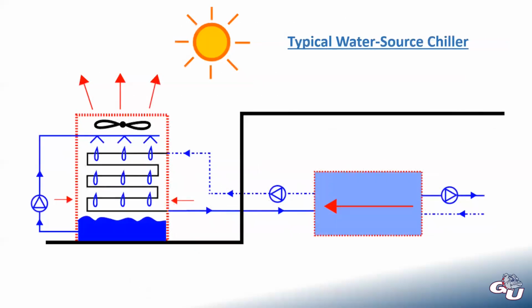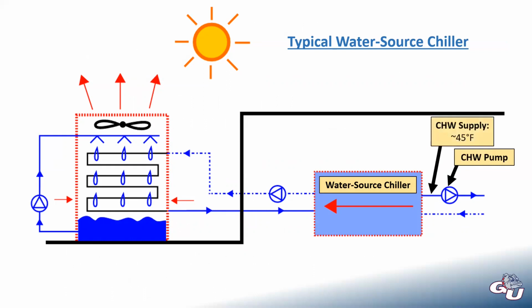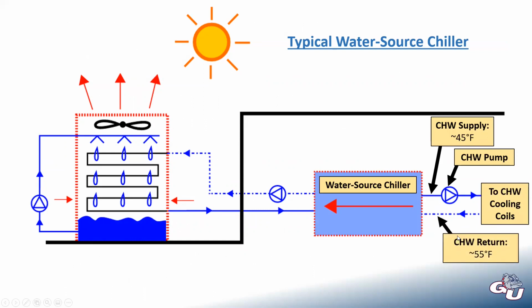Here's another one of my sketches, but you're quickly going to realize there's a lot more going on with this system. We have our water source chiller, which is inside the building. We have our chilled water pump, which is sending out 45-degree water, going out to the chilled water cooling coils, coming back a little bit warmer, goes through the chiller where we chill the water down, and then it sends it back out. On this side of the system, everything is identical compared to an air source chiller. Fundamentally, there's nothing different about this side of the process.